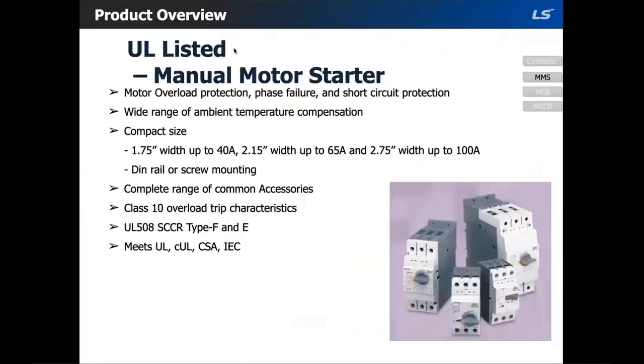Okay, so the next product that I'm going to talk about is the manual motor starters. Manual motor starters are electromechanical protection devices for a main circuit. They are used mainly to switch motors manually on and off and protect them fuseless against short circuit, overload, and phase failures. Fuseless protection with manual motor starters can save cost, space, and ensure a quick reaction under a short circuit condition by switching off the motor within milliseconds. So fuseless starter combinations are set up together with a contactor.